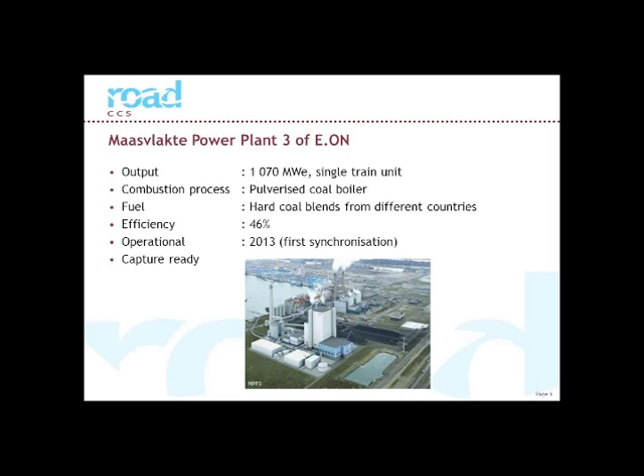Okay, thank you very much, Andy. This is Hette speaking from now on. Well, this is just a picture of the Maasvlakte power plant of E.ON. In front, you see the Maasvlakte power plant number 3. That's being built at the moment. It's a 1,070 megawatt electrical single train unit. Single train means one boiler, one steam turbine, one generator. It's fired with pulverized coal. The coal comes from all over the world. The efficiency is over 46%. The first synchronization was in 2013, but the commissioning is still continuing in the first half of this year.